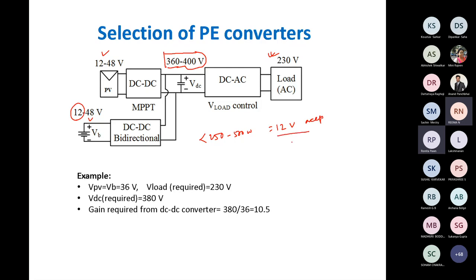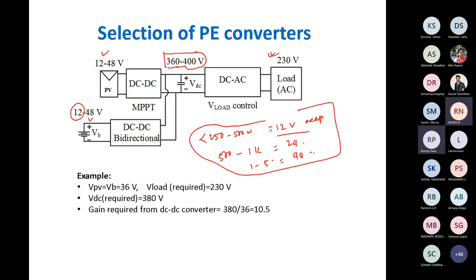You see several inverters at home, Microtek, Sukam, Luminous, etc. If these are around 150 VA to 500 VA, they use a 12 volt battery. From 500 to maybe 1 kVA, they may use 24 volt. From 1 kVA to 5 kVA, they will use 48 volt, etc. So this is product-level information about what battery voltage you can go with depending on power.